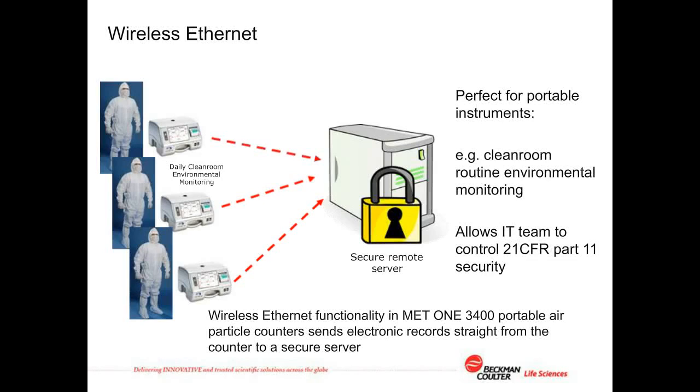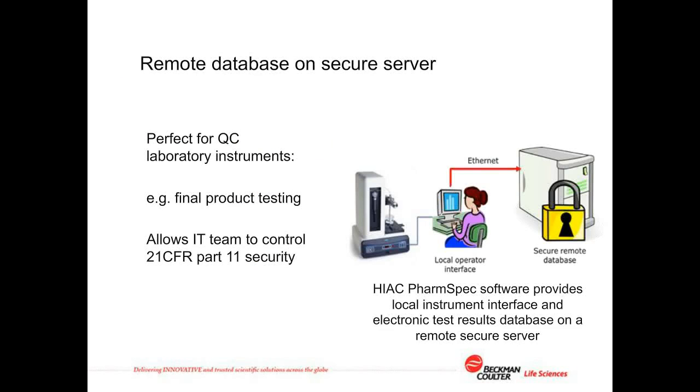So here the clean room technician is carrying the portable particle counter around, carrying out the environmental monitoring using the electronic SOP pre-programmed in the counter, and they're exporting the data via wireless Ethernet straight to a secure server somewhere on the network, which allows the IT team on that site to apply the correct security controls for 21 CFR Part 11 compliance.